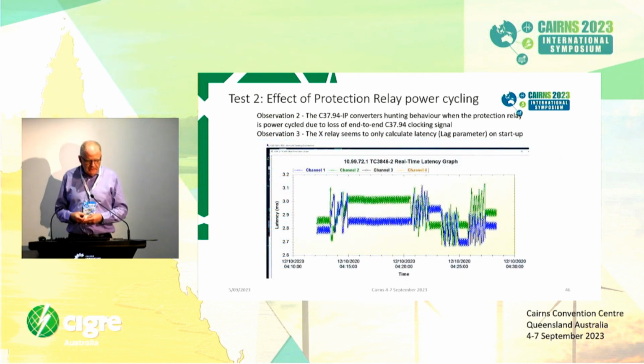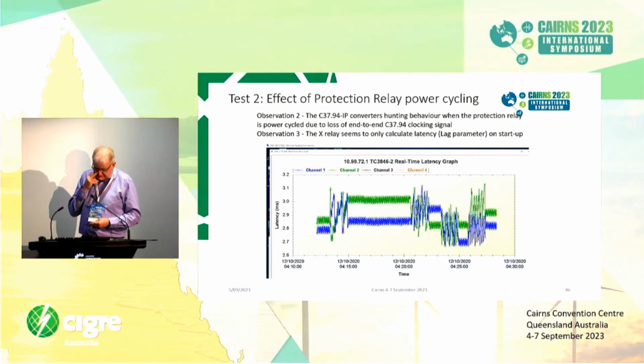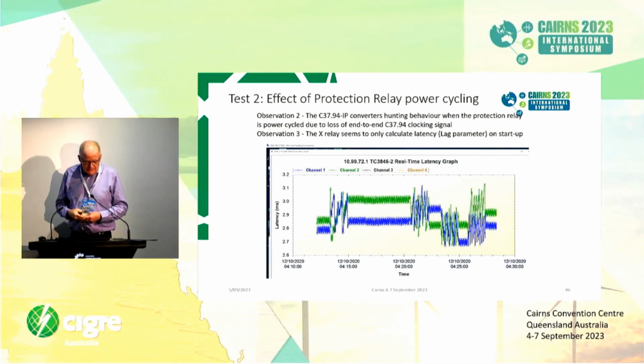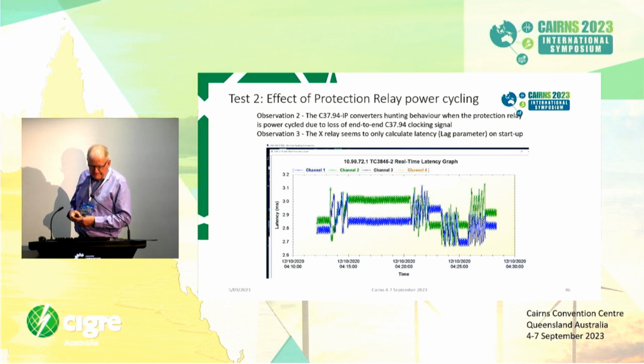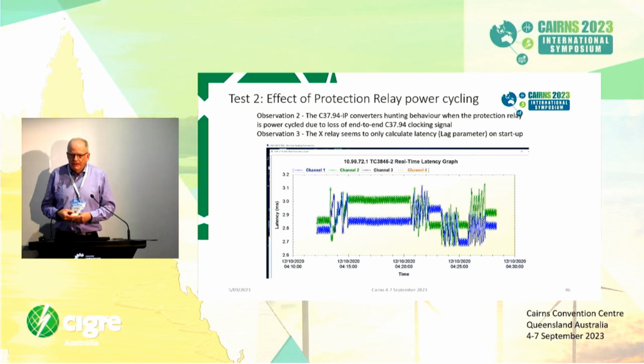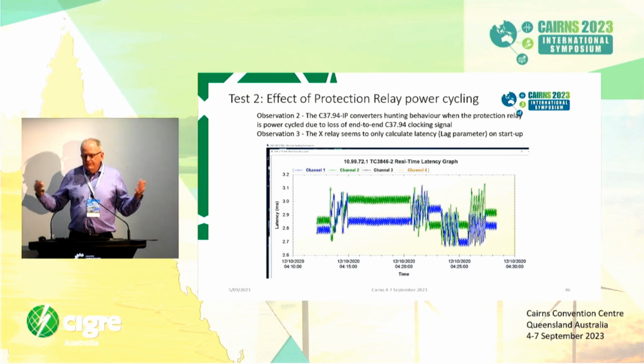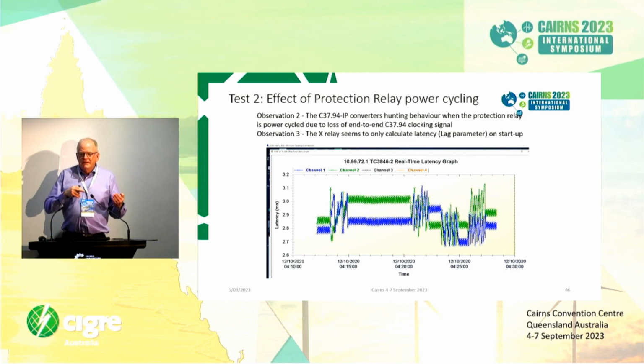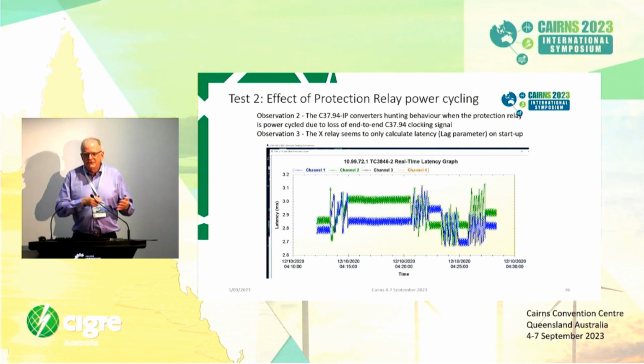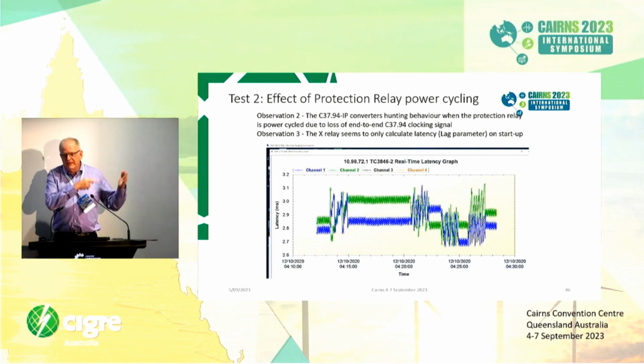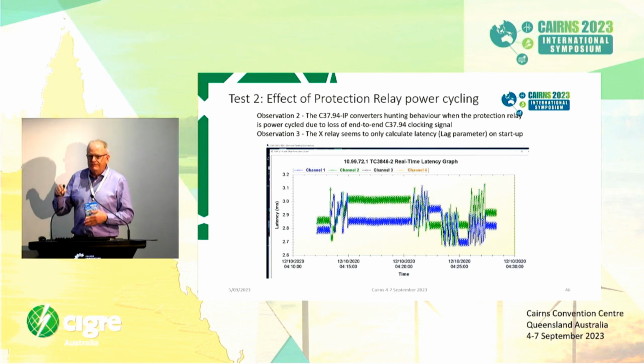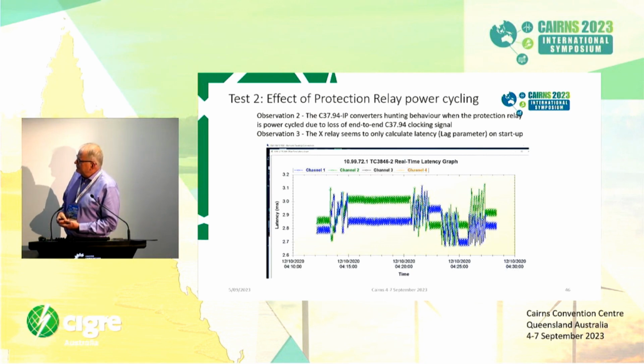This is once again part of the test 2 test results. So we've observed that on the C37.94 converters, if the network's normal, you've got your protection relays powered up, they're providing that C37.94 time synchronisation, being looped back into the converters, and then the system's normal, so the time distribution's working in a loop throughout the entire circuit.